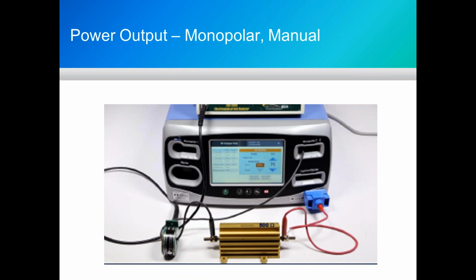So here we just have a quick display showing a cable coming from the active output of monopolar 2 through a separate current transformer to one end of the power resistor, and then a return back to the patient return. One thing to note here is there's unfortunately plenty of opportunity to become part of the circuit yourself, and that's something that you really would like to avoid.